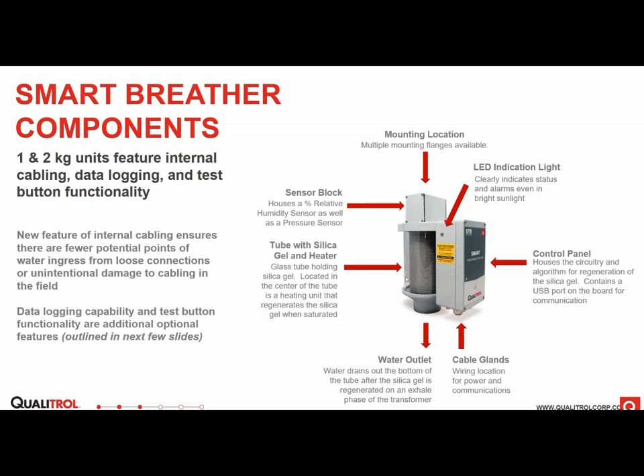Here in the middle is the glass tube, and inside that glass tube is the silica gel that is located in a mesh with the heater inside of that. The water outlet on the bottom. This has a stainless steel filter on the bottom to prevent any bugs or big particulates from getting in the breather and contaminating the silica. And then the front here is the IP65 control box. And then another change that you might notice here from our previous generation is that we went from 3 front LEDs to a single side LED. And we'll talk a little bit more about that in a few slides.